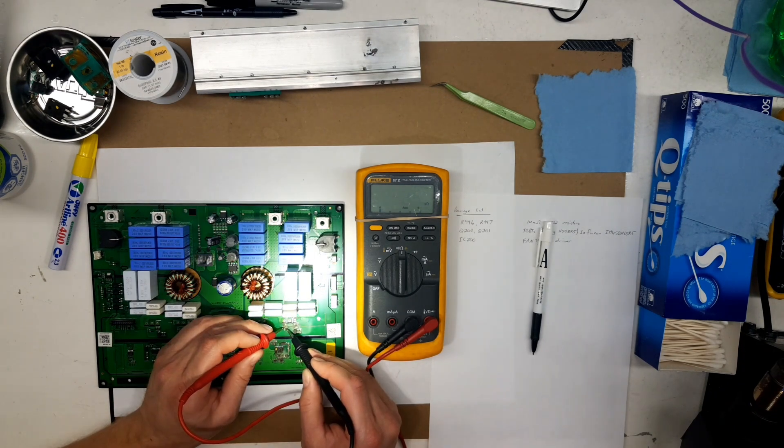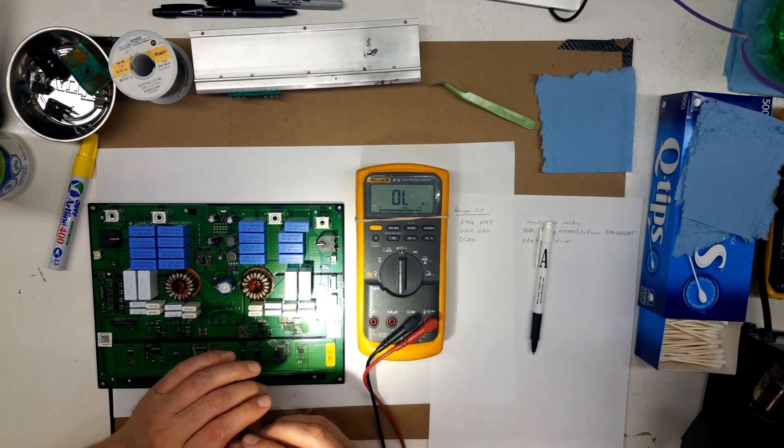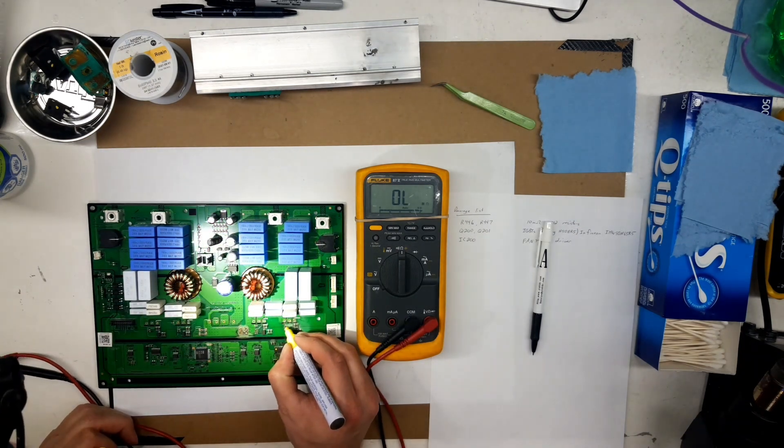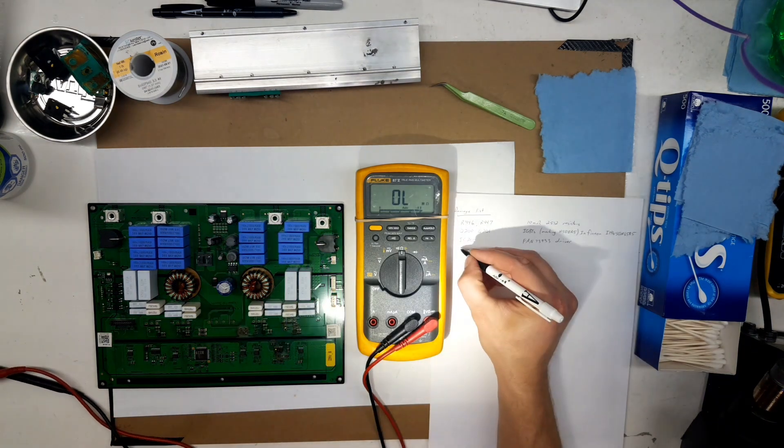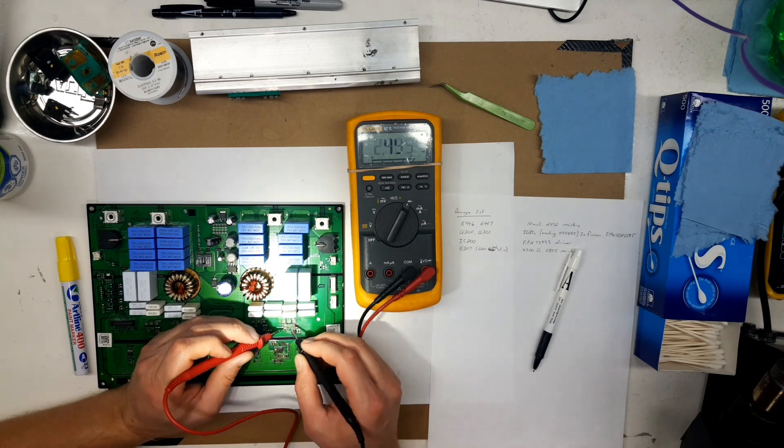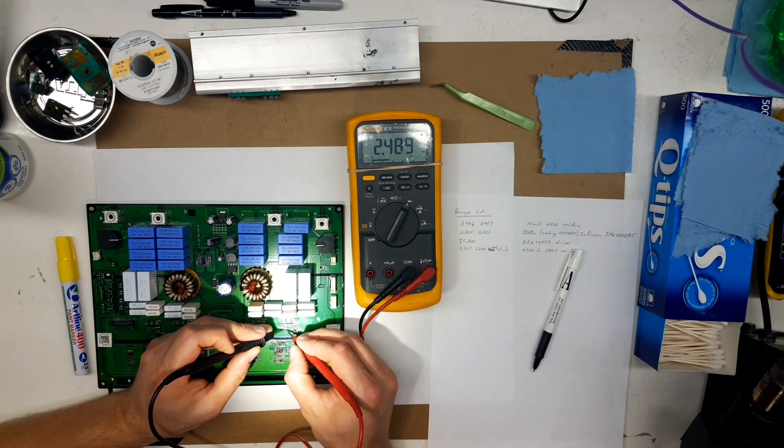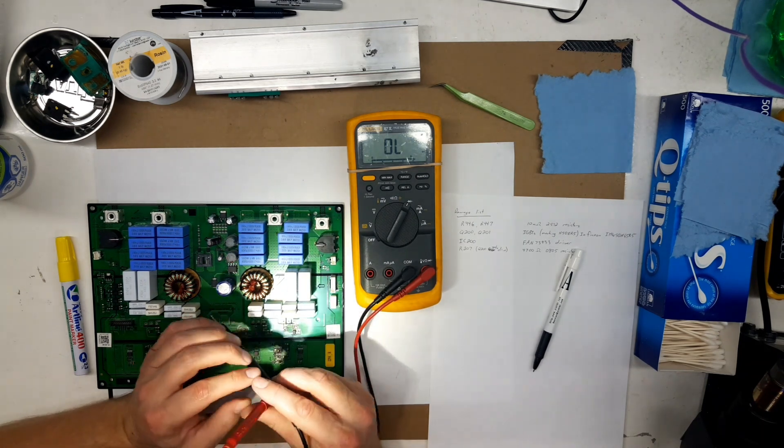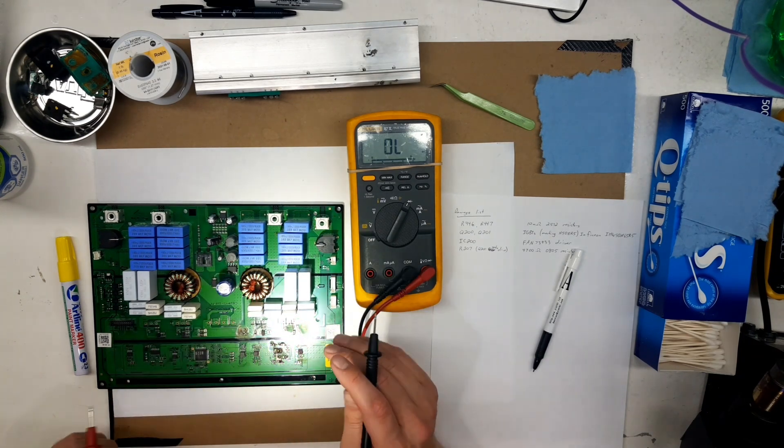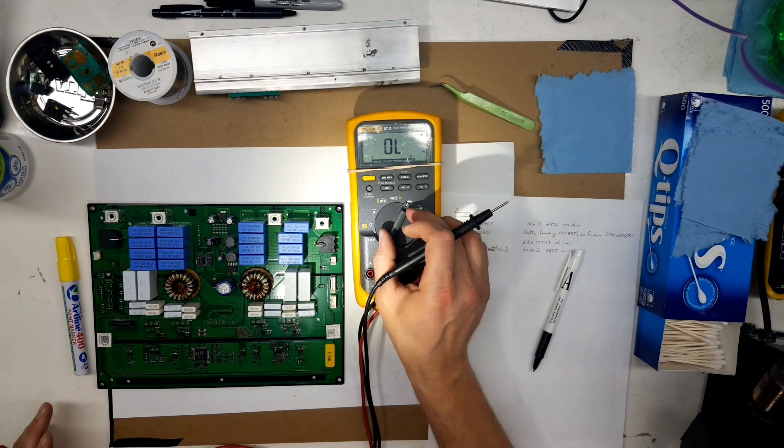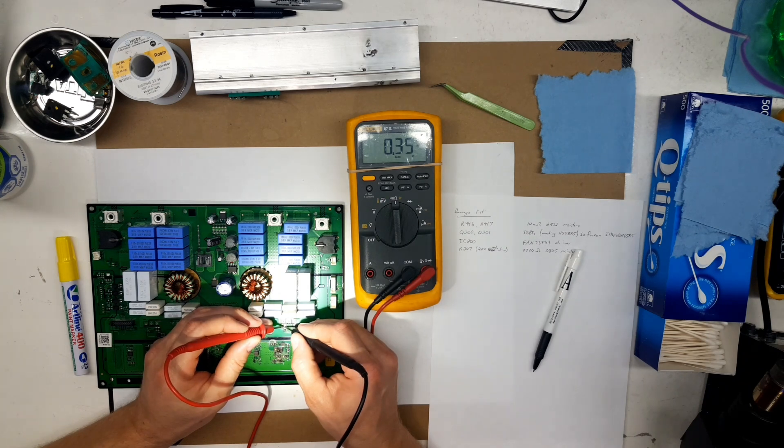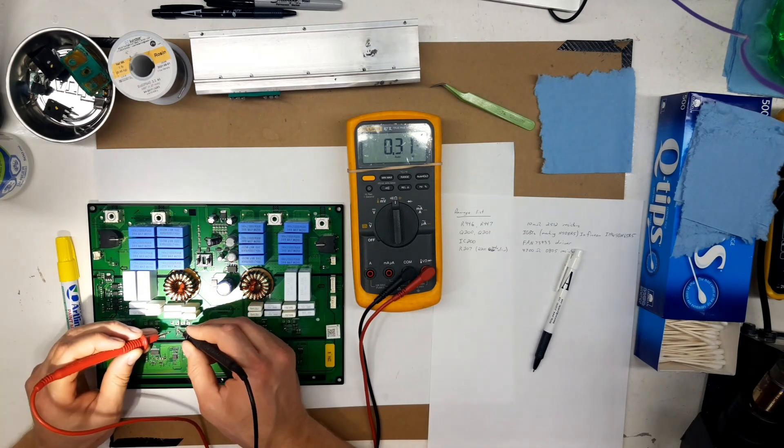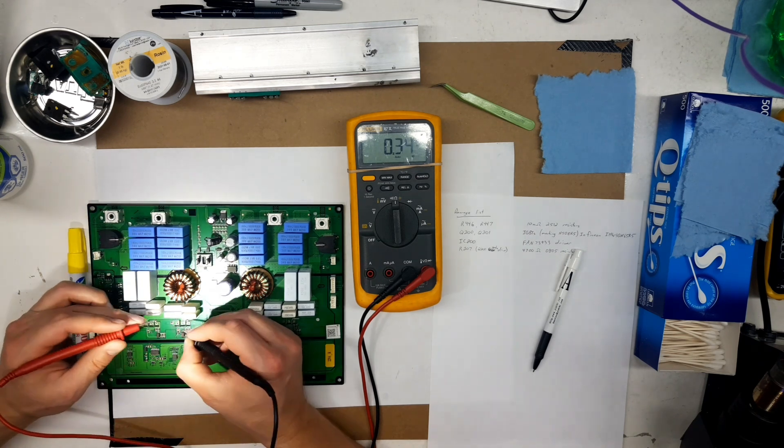So this is all the circuitry between the driver chip and the IGBTs. There's several resistors and diodes and zener diodes and capacitors and whatnot surrounding the IGBT, which controls how fast it turns off, how fast it turns on, that kind of thing. As you can see there's quite a few components which are blown up. What I like to do, other than writing everything down on a list, because all these parts will need to be changed if we're going to get this board working again, when I do find a component that doesn't work, and I know it to be bad, I will put a dot of yellow paint on top of it. It's hard to erase and easy to see. It makes things a little easier later on when you're stripping the bad components off and replacing new ones.